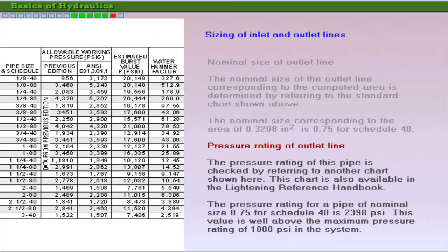To determine whether the given wall thickness is sufficient, refer to the pressure ratings chart for welded connections in seamless steel pipes in the Lightning Reference Handbook. The pressure rating of 2,398 PSI of the pipe is more than the maximum pressure of 1,000 PSI in the system. Hence, a pipe size of 3/4 of an inch for Schedule 40 is suitable for the pump outlet.